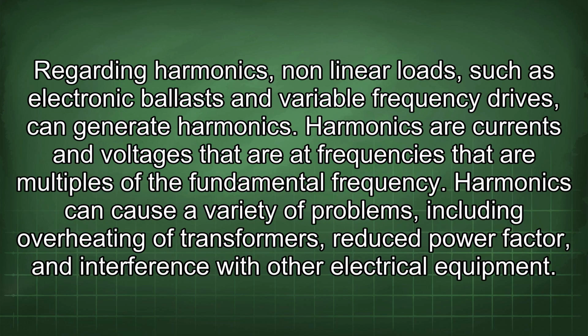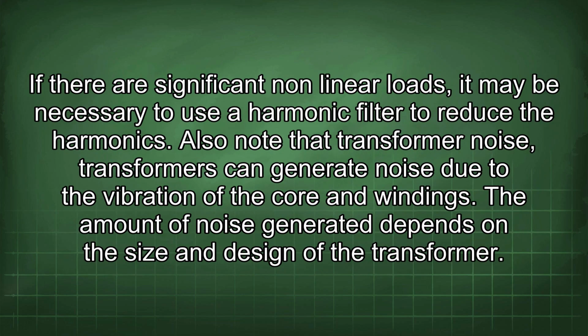Regarding harmonics, nonlinear loads such as electronic ballasts and variable frequency drives can generate harmonics. Harmonics are currents and voltages that are at frequencies that are multiples of the fundamental frequency. Harmonics can cause a variety of problems, including overheating of transformers, reduced power factor, and interference with other electrical equipment. If there are significant nonlinear loads, it may be necessary to use a harmonic filter to reduce the harmonics.